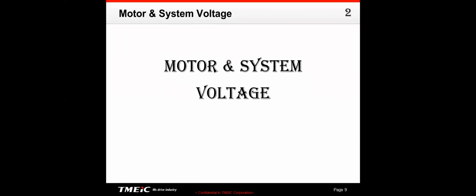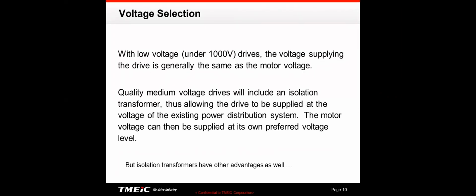Now, next, let's look at motor and system voltage. If you have a low voltage drive, typically, if you've got a 208 volt system, you get a 208 volt drive, you feed it with 208 volts, it puts out 208 volts, and you use a 208 volt motor. That's not 100% true, but it's like 99.9% true. With medium voltage drives, that is not true.